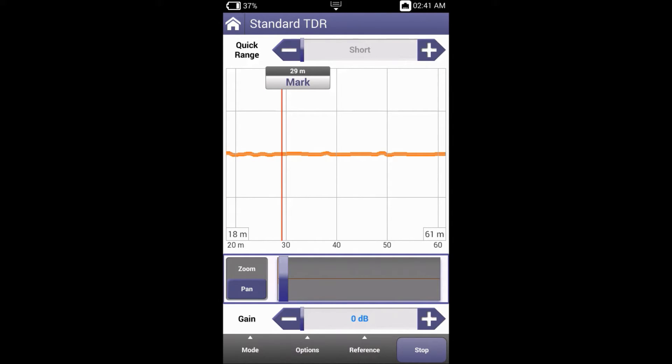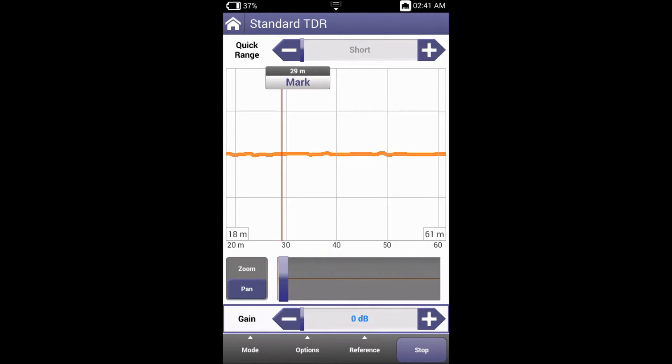Gain controls the amplitude of the transmitted pulse. The plus sign increases the gain, while the minus sign decreases. Use only enough gain to clearly see the event. Using too much gain can distort the trace.